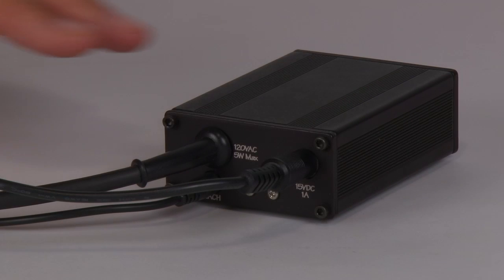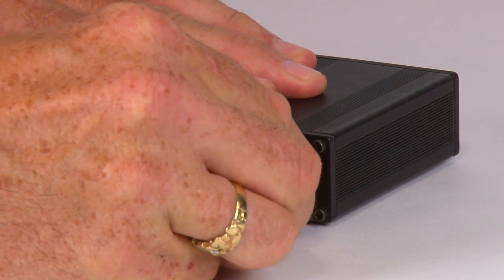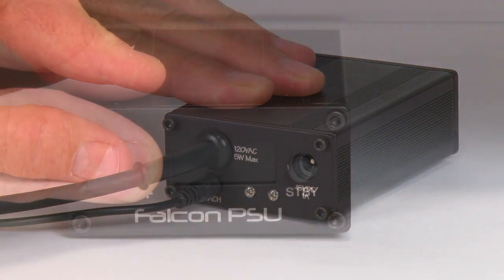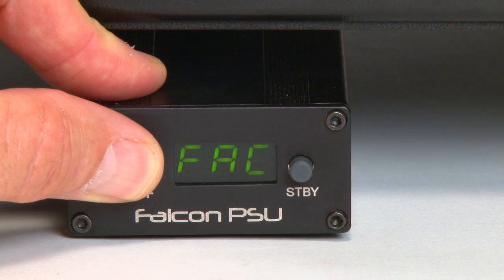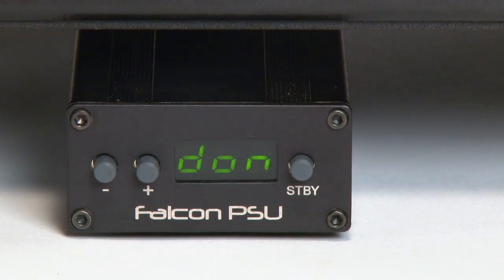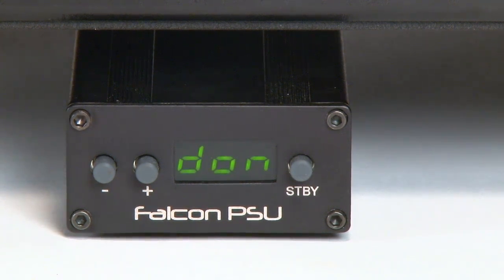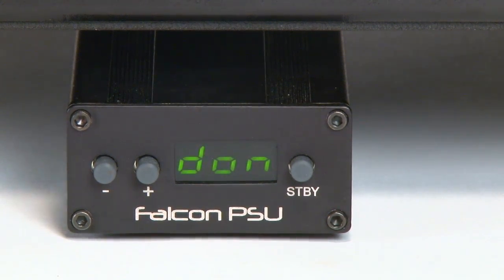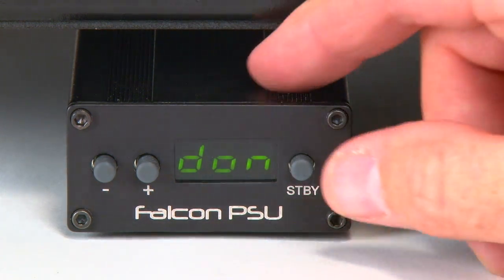Factory default mode. To restore the Falcon operating parameters to the factory defaults, remove the power plug. Press and hold the plus and minus buttons while inserting the power plug. The display will show FAC to indicate factory default programming mode has been entered. Release both buttons and the display will show DON to indicate factory programming is complete.